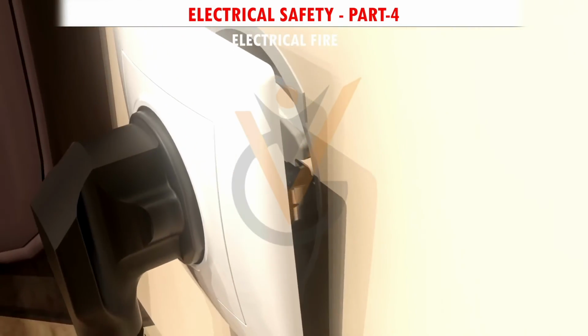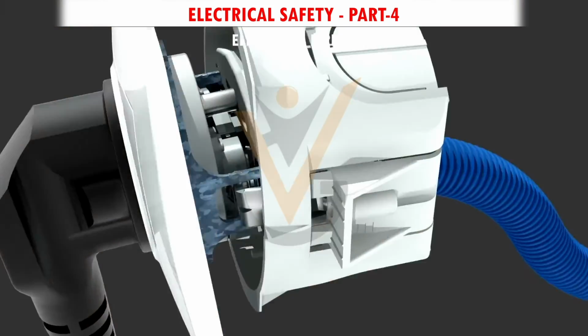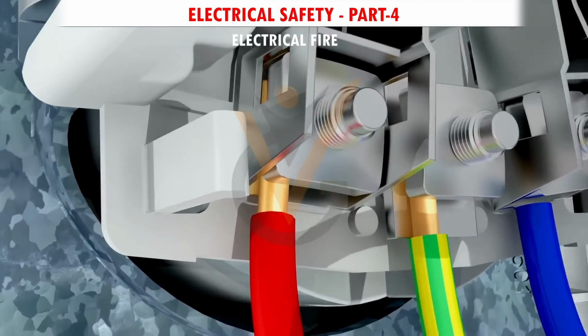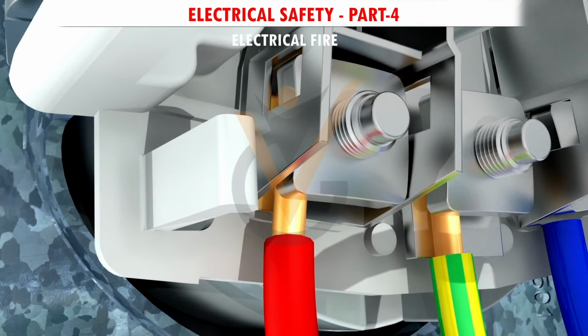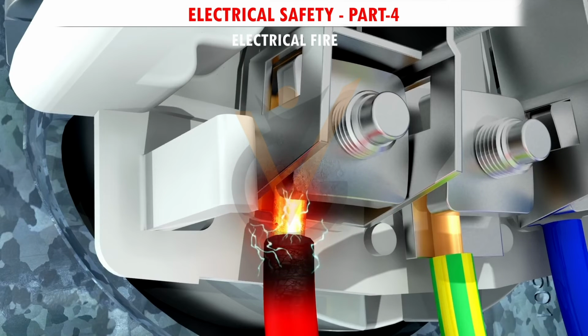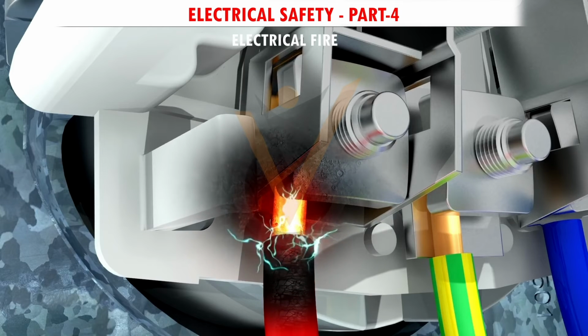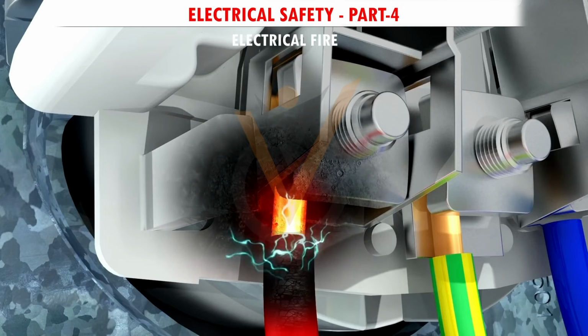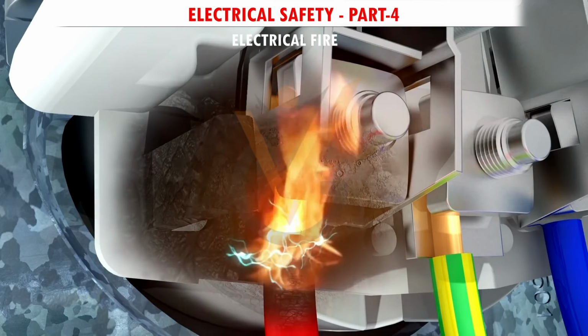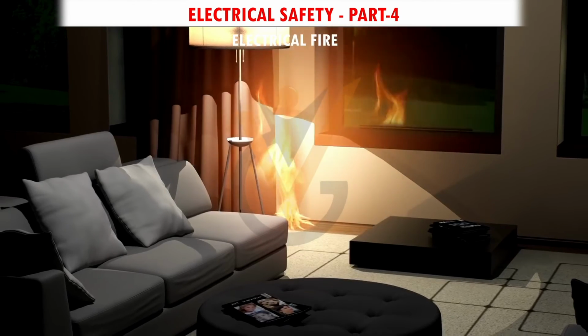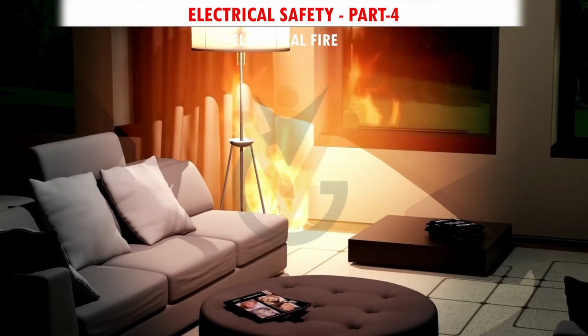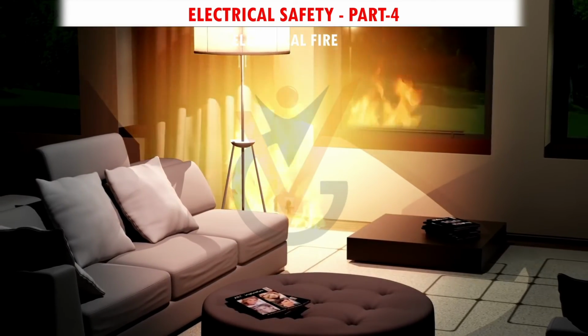Any of these factors could cause connections inside the wiring to break down, triggering a fire. The connections gradually pull apart and overheat, burning the surrounding cable insulation and socket. This transforms the insulating material into carbon, which acts as a conductor and carries some of the current traveling through the wires, creating electric arcs. Eventually, the cable insulation and socket catch fire. The fire can then easily propagate throughout the room, spreading to a nearby curtain, the wall covering, the furniture, and so on.